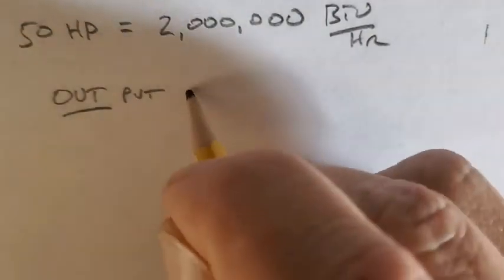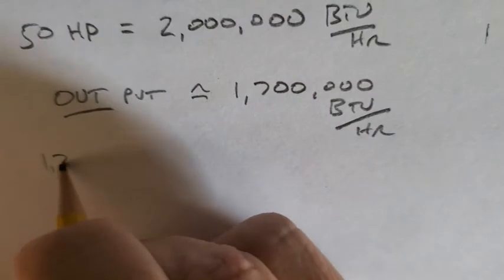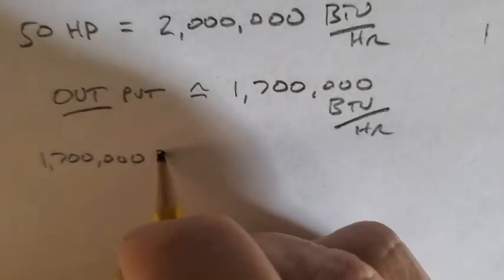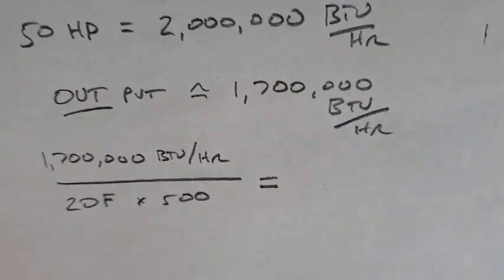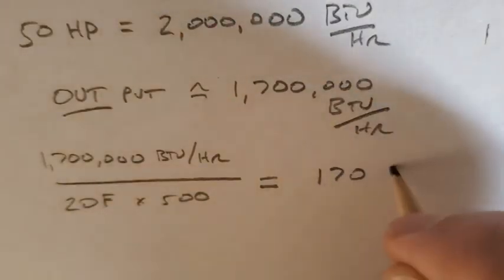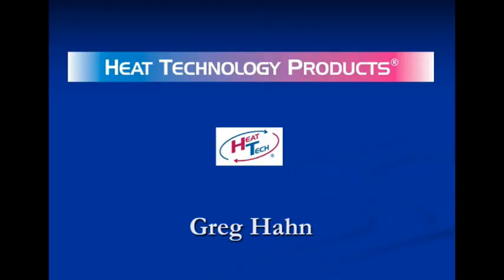Let's finish the math problem. Let's use a 2 million BTU boiler with an output of 87% of that, or about 1.7 million BTUs per hour. And let's assume we measured our delta T at 20 degrees. Inlet 160, the boiler raising that to 180 degrees, equals 170 GPM. And that's how you can use delta T to estimate your flow.